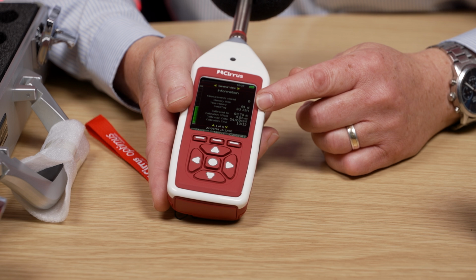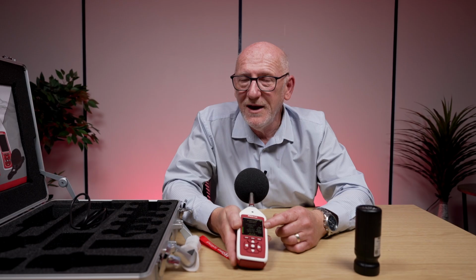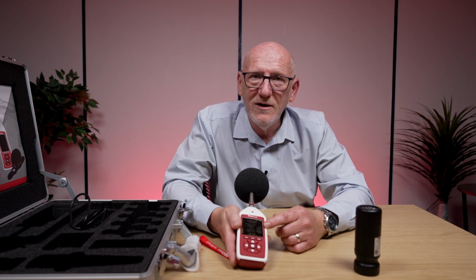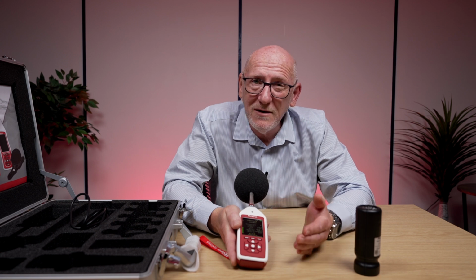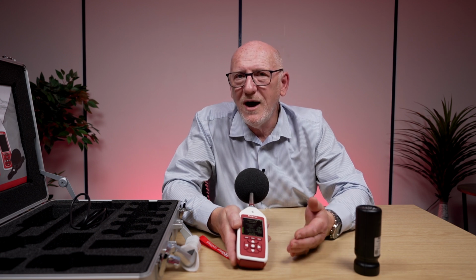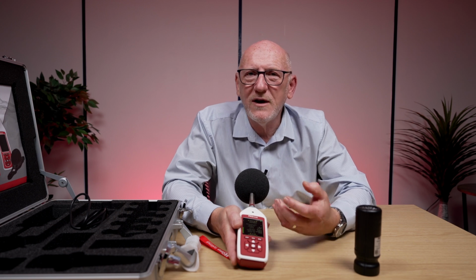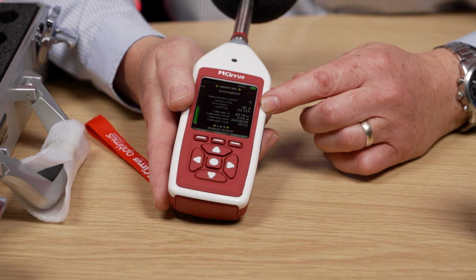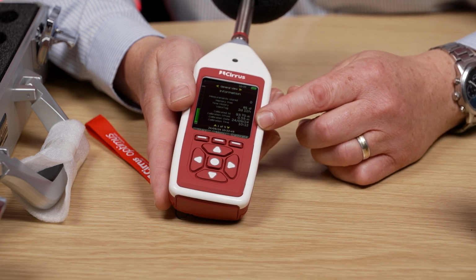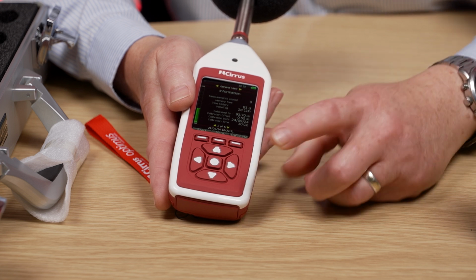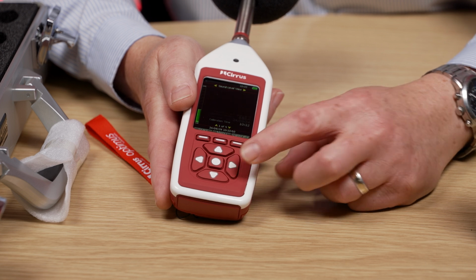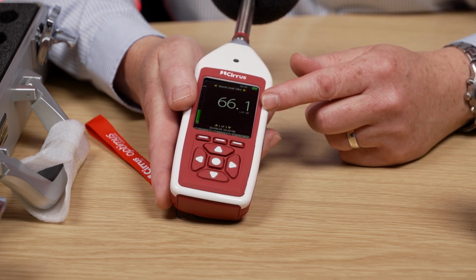And we've also got a small amount of audio in here. Depending on the meter that you have, if it's an environmental Optimus Plus, you can store actual audio. But even if it's just an industrial meter, you can store your voice at the start of every measurement. So we have some capacity for that. It's showing me the last time it was calibrated, etc, etc. And if I go to the right again, I'm back at the first screen.